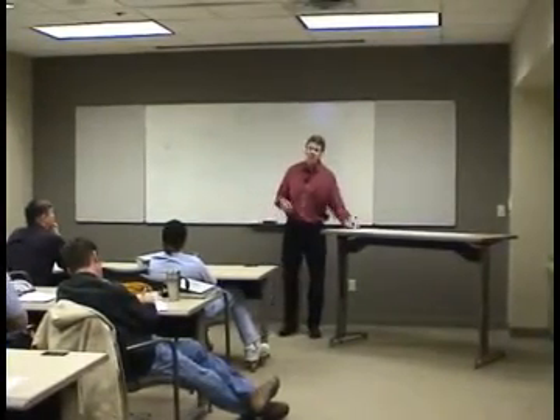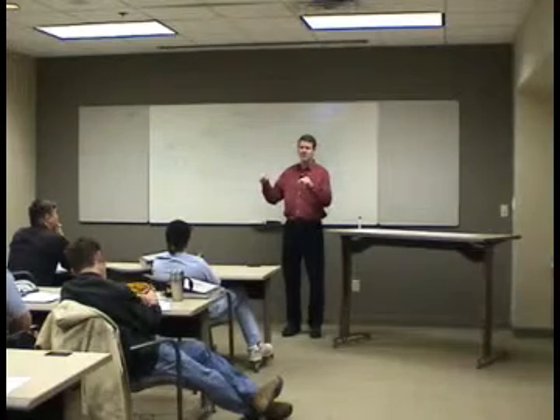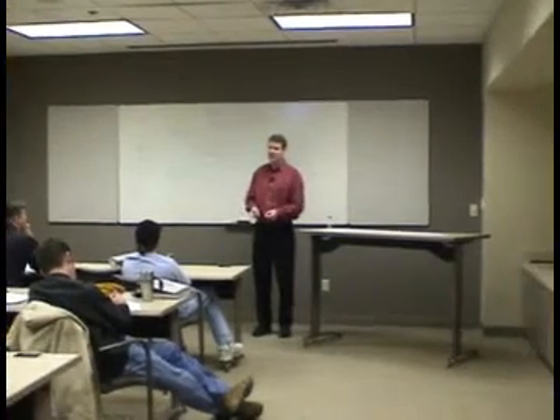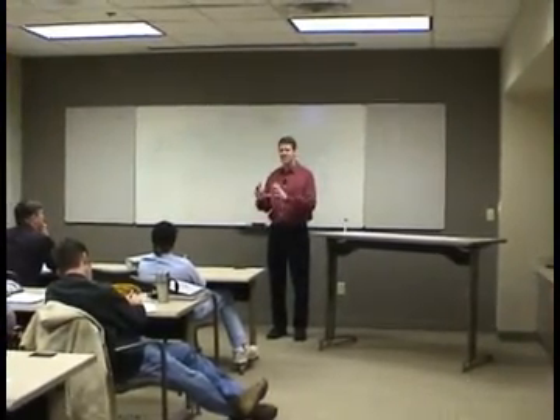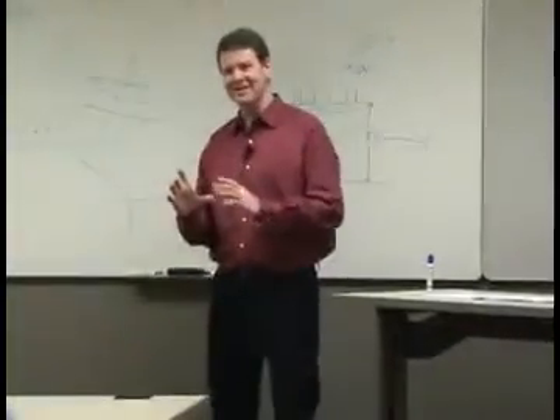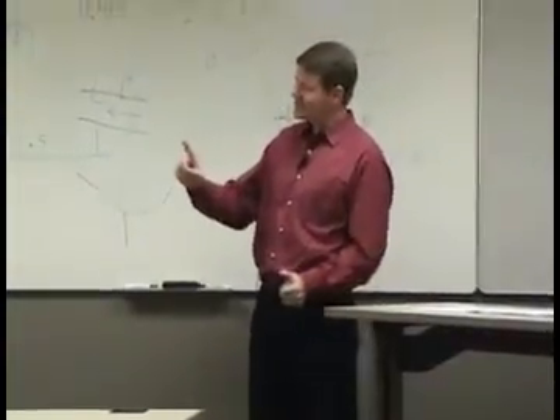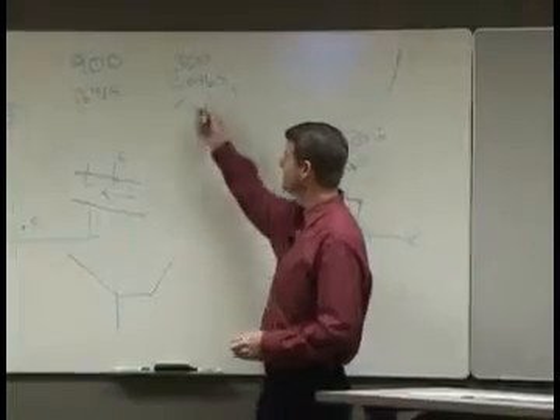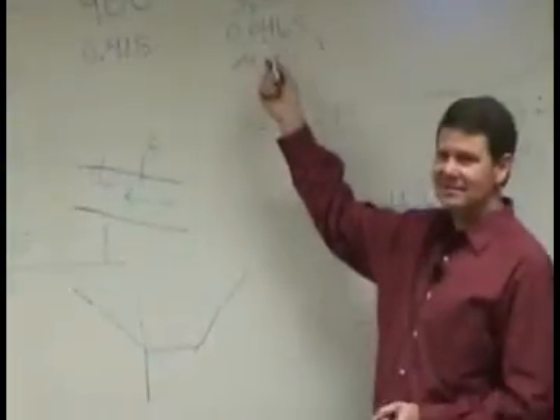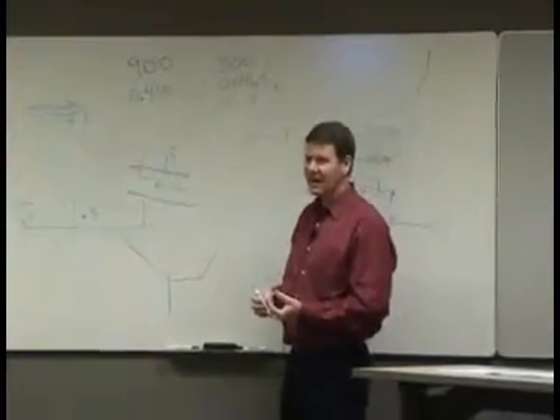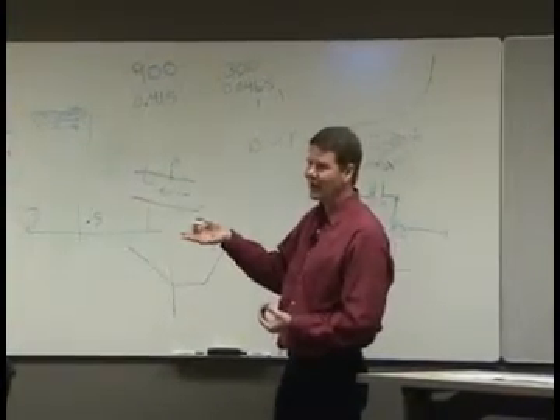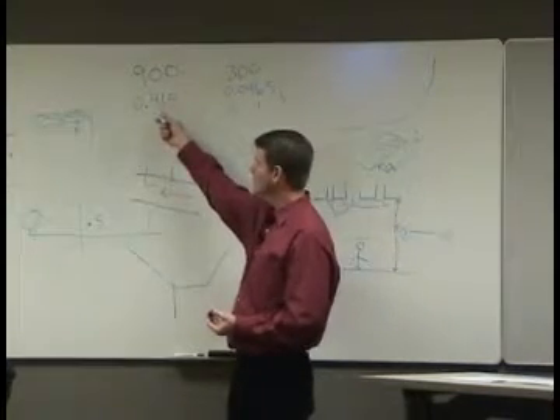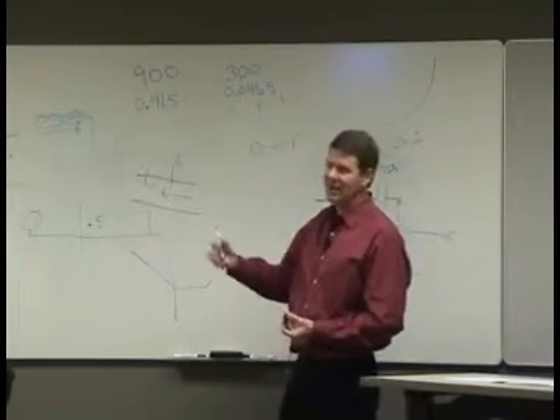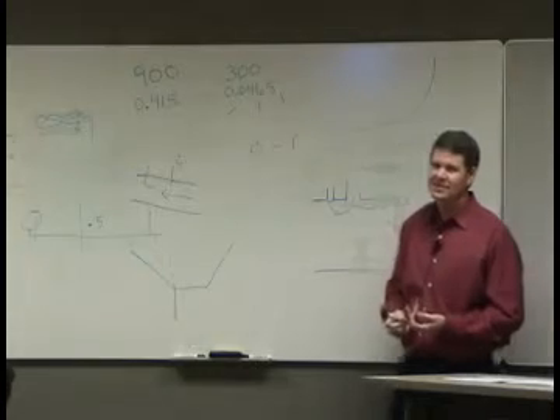So you pull the tubes off, put your magnehelic on. You know, you got a nice 0 to 5 inch magnehelic. Yeah, really. And the needle just barely quivers. Well, if all you got's minimum CFM, you got 0.0 something, that might be right. Try and get the box wide open so you get up to where you're reading something above 0.1.